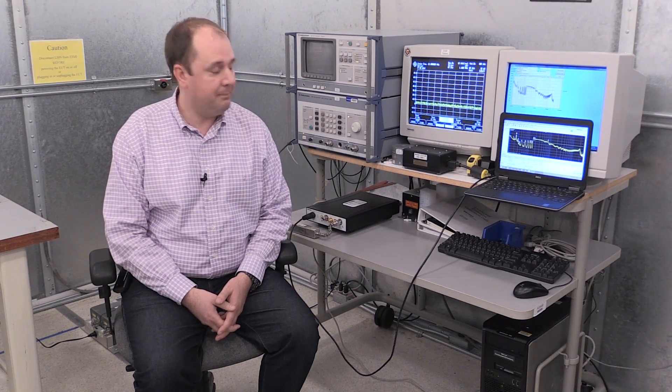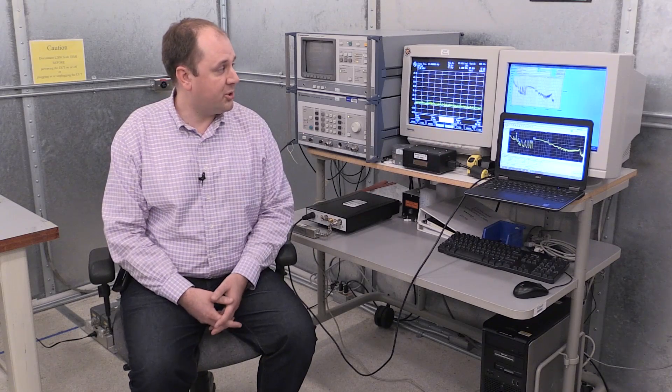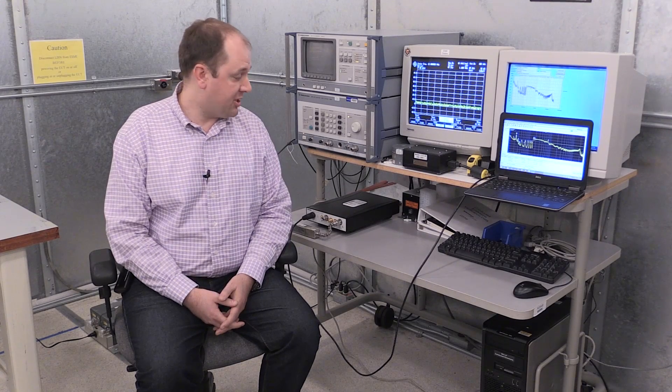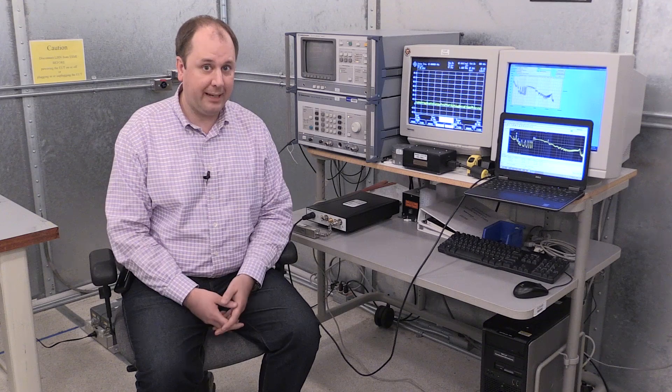We're still doing the conducted emissions test per CISPR 11 with our device under test. The line impedance stabilization network or LISN is directly behind me. We can see that the results track very closely and we'll take a closer look at those results here in a minute, but it's the same kind of test for conducted emissions. I haven't changed anything for the setup and I'm able to get the same results with the RSA 600 series.